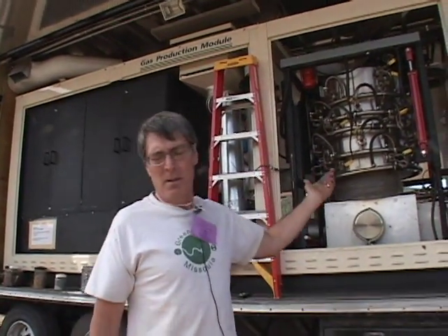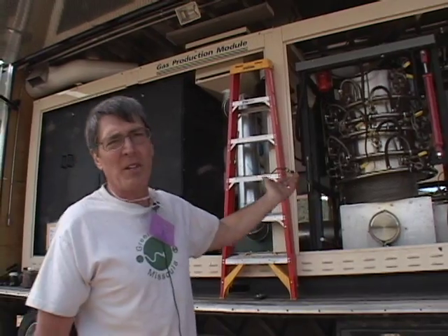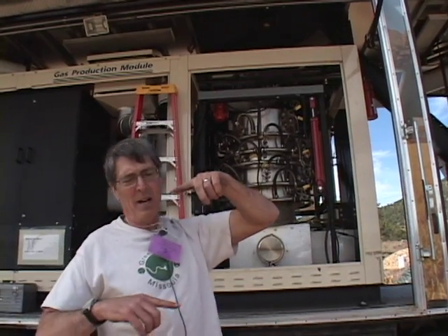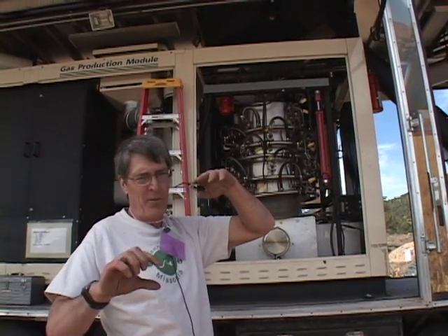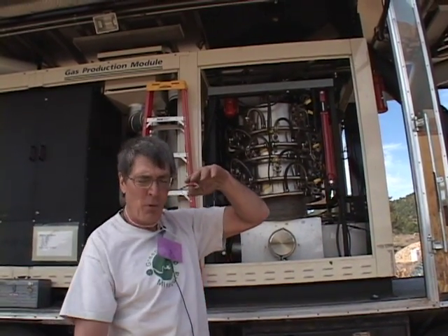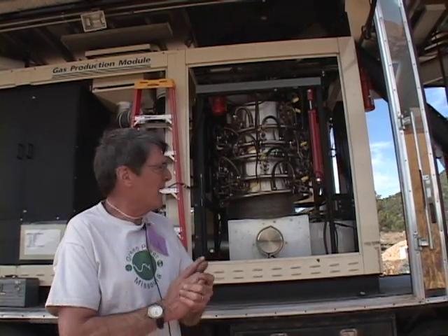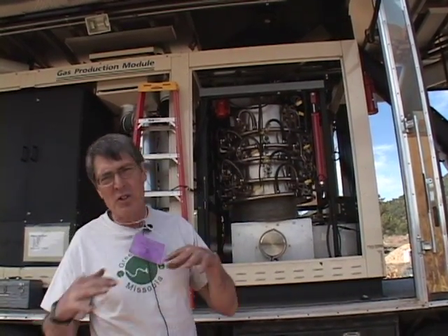This is the gasification reactor. It's basically just a big pipe, and the pipe is full of wood chips. There's about a 6 to 8 inch layer of fresh wood. There's a small flame front at the bottom of that, and the whole rest of the length of that reactor is full of hot char. The char is about 800 degrees C, and we control that through differential injection of oxygen.